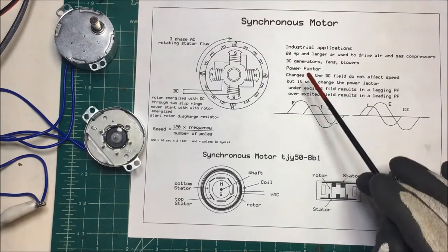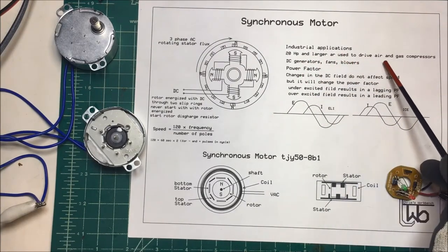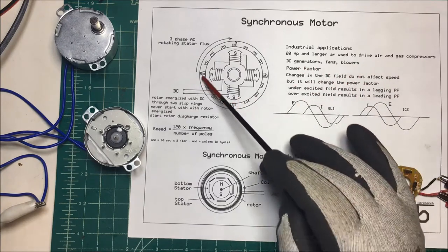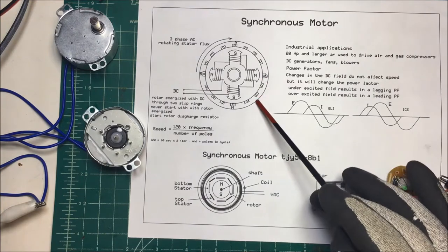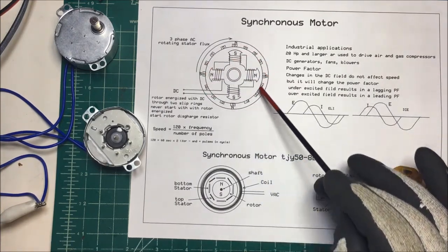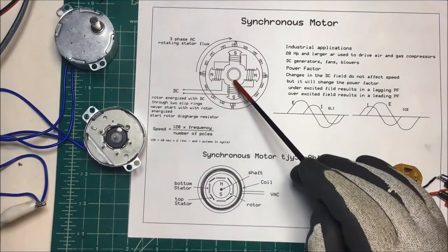Let's talk about synchronous motors. In industrial applications, they're usually 20 horsepower and larger, and they're used to drive air and gas compressors, DC generators, fans, and blowers. The stator out here is just like the stator in a three-phase squirrel cage motor, but the rotor here is powered with DC and it's powered through a set of slip rings.